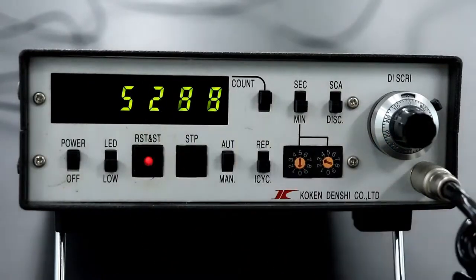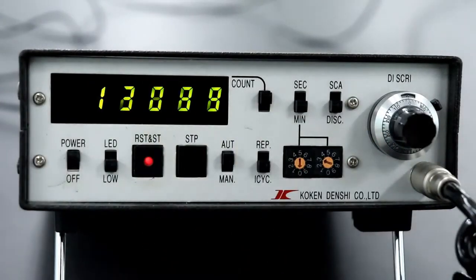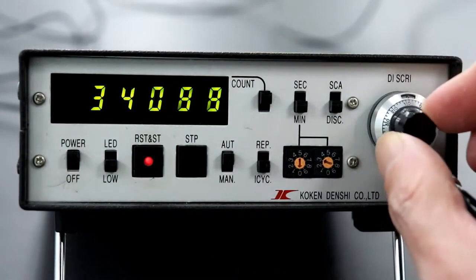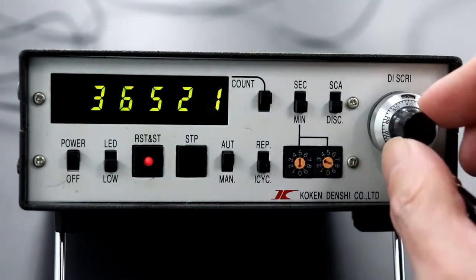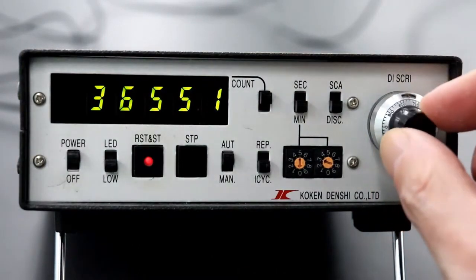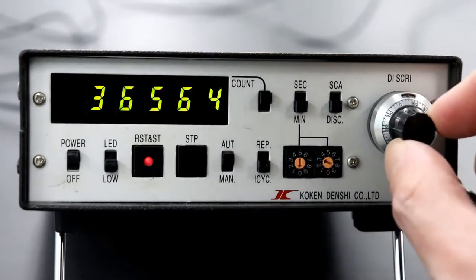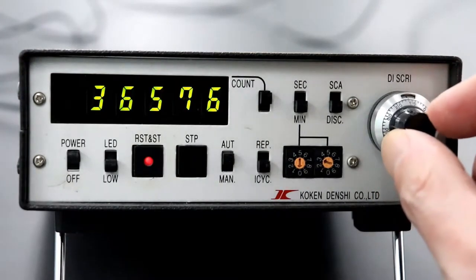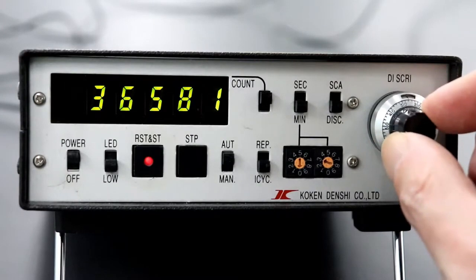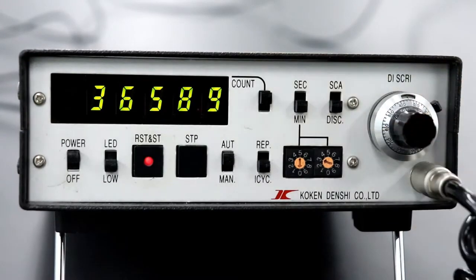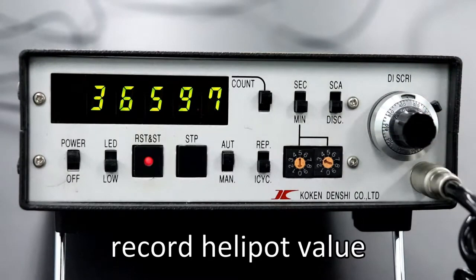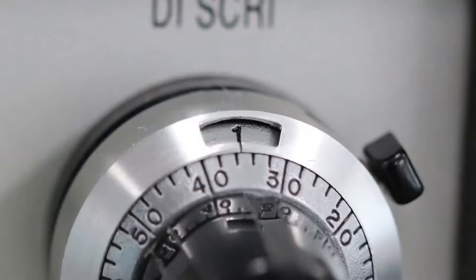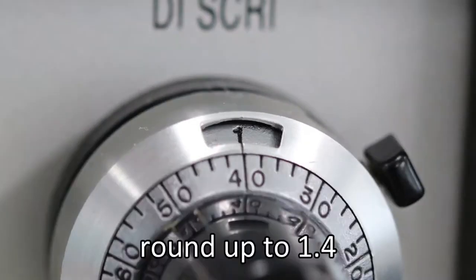At beginning, the value will rise vigorously. As you turn the helipot, the numbers on the display board will gradually change more slowly. When the number of counts per second reaches a few times, stop turning the helipot and record the helipot value at that time. In this case, it is about 1.35. To make it a round number, round it up to the first decimal place and set it to 1.4.